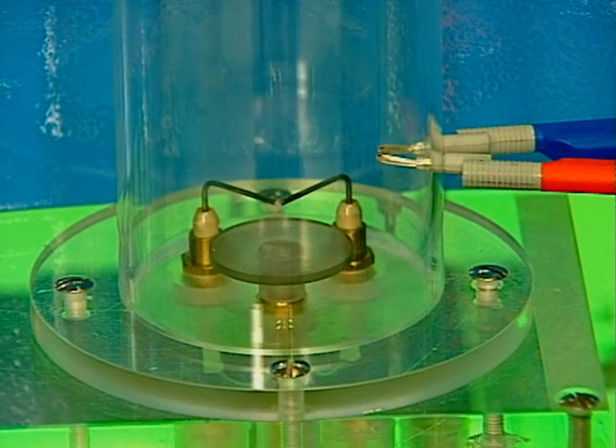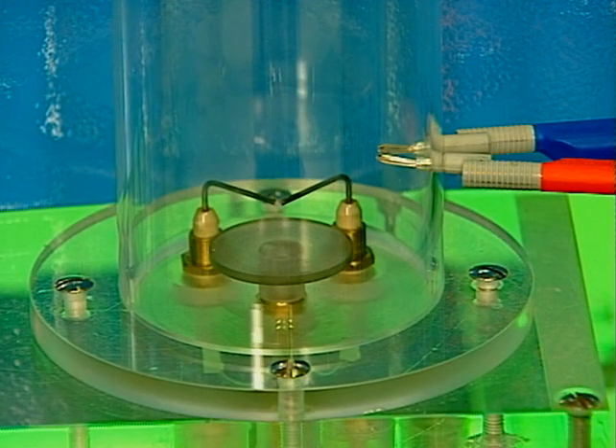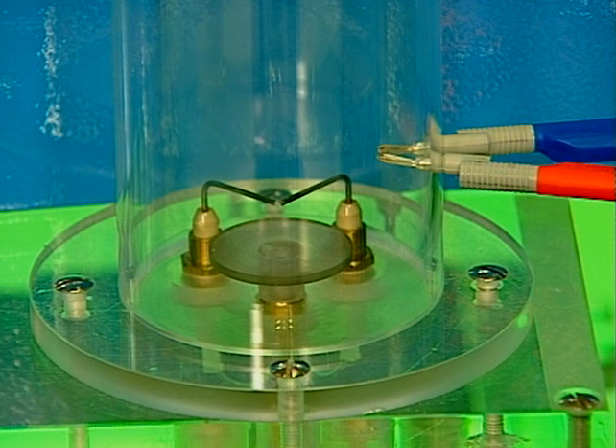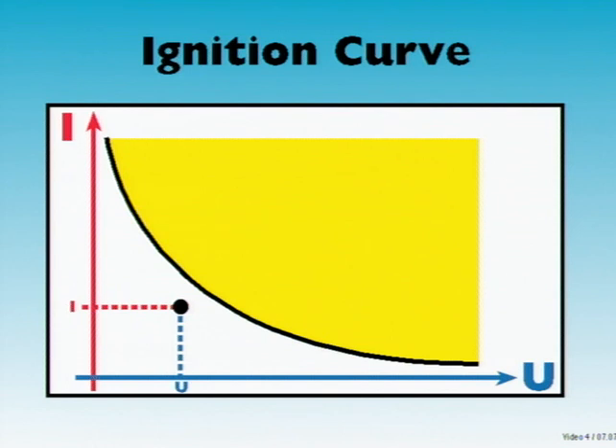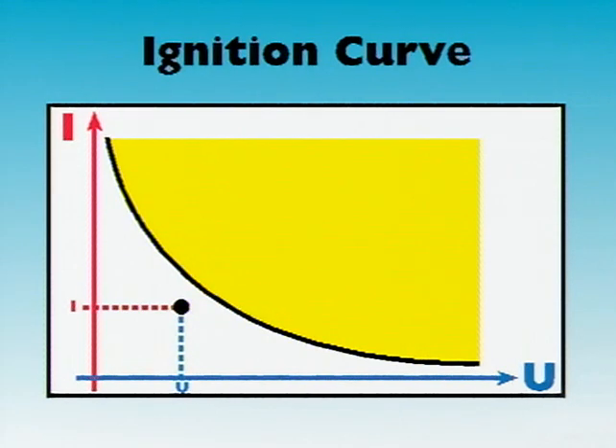So that no spark is created that can lead to an explosion, the energy must be kept below the ignition energy of the mixture-specific limit ignition curve. This means that both the voltage and the current values in the explosive environment must be limited.